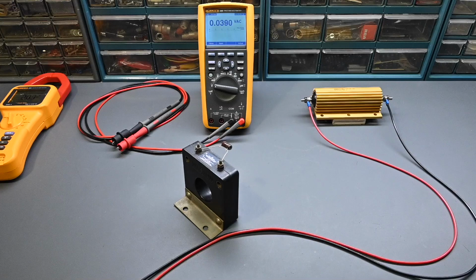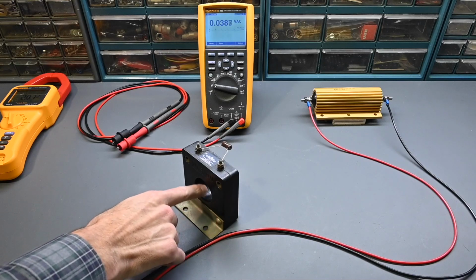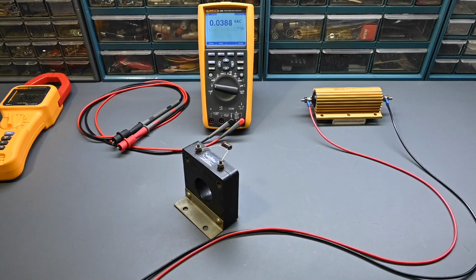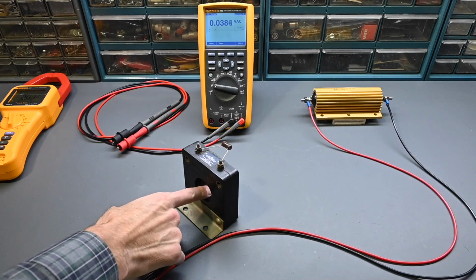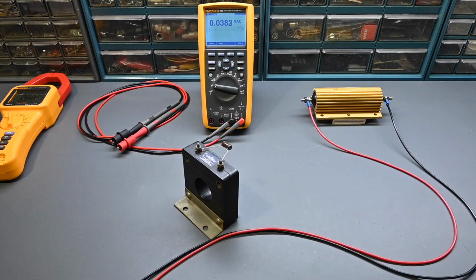Now, all current transformers require that a wire be routed through the window of the transformer. So this hole right here is known as the window. So the wire that you're trying to measure the current on needs to pass through this window. And that, of course, makes the current transformer less than ideal in some applications, because you may not physically be able to move the wiring over to the transformer and route it through the window. Oftentimes it would be more appropriate to use a current clamp. But current transformers certainly have their place.